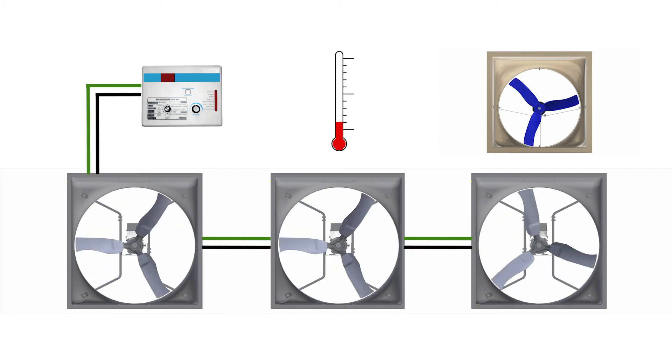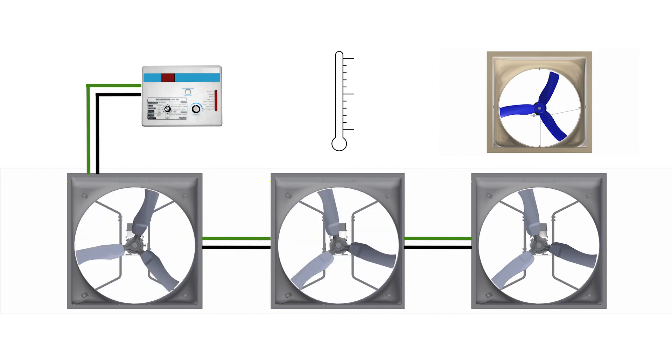Direct drive variable speed fans deliver superior CFM to watts rating when running at lower speeds. At 50% capacity, an Infinity fan can reach efficiencies as high as 36 cubic feet per minute per watt.